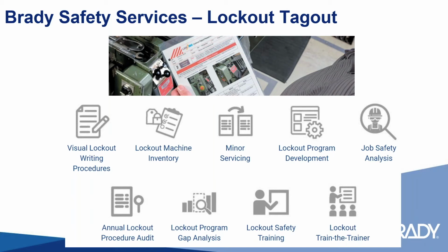The next level for lockout tagout compliance is really having machine-specific procedures written for your technicians to use when working around that equipment. It gives them step-by-step instructions on how to safely de-energize equipment and make it safe to work on. That's what these lockout procedures are for. It's an OSHA requirement and part of the safety services we provide for lockout tagout compliance.